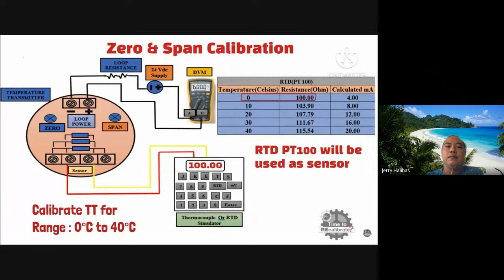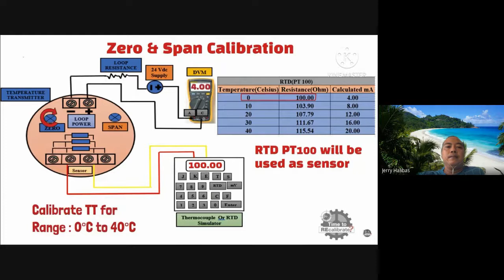For example, if the measured milliampere value is 3.96, then rotate the zero adjustment screw in the clockwise direction until it becomes 4 milliamperes. Once you are done with zero adjustment, set 115.54 ohm resistance value in the simulator, and feed this resistance value to the temperature transmitter. After this, measure the milliampere value in the DVM. The measured milliampere value should be 20 milliamperes. If it is not 20 milliamperes, adjust it to 20 milliamperes.